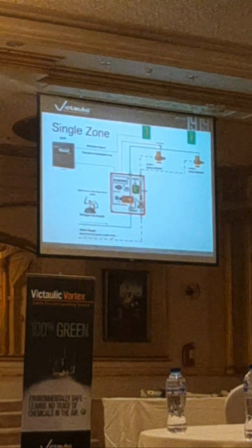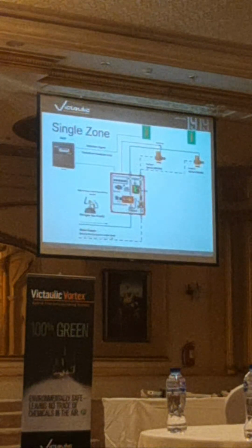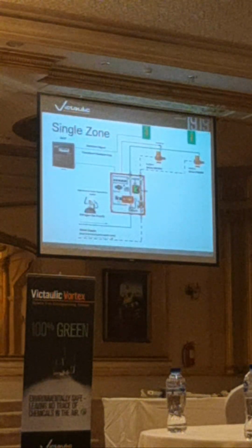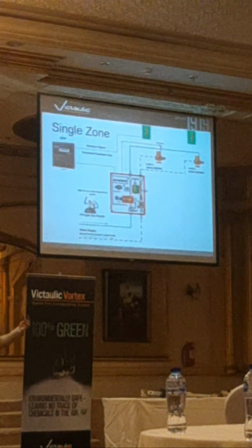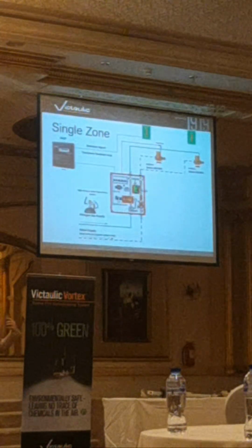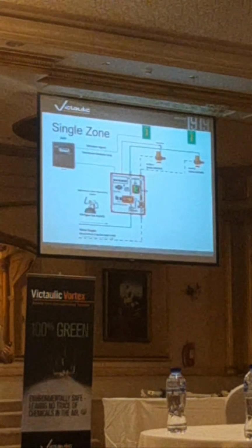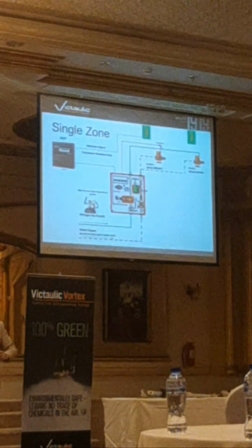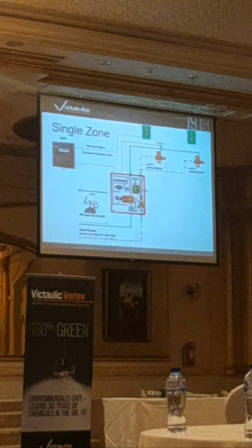Here's where it's going. You can see the green line from your cylinders, 200 bar, is going up until the panel. And in the panel, we're going to reduce the pressure from 200 to the working pressure of 1.7 bar. Now, your colleague has just left, but I'll repeat it maybe when he's back.